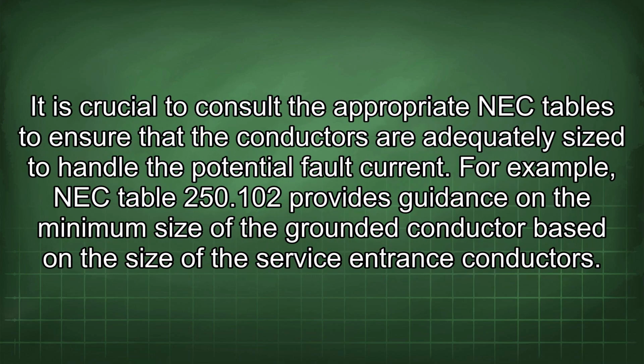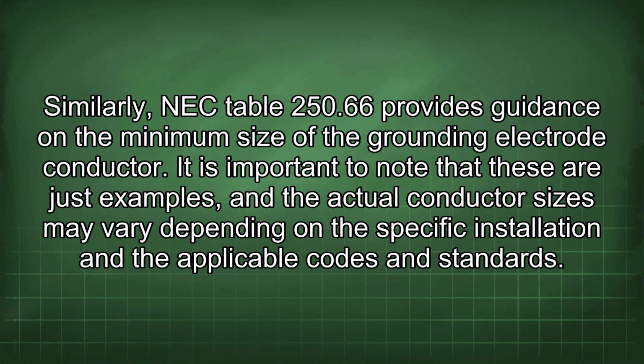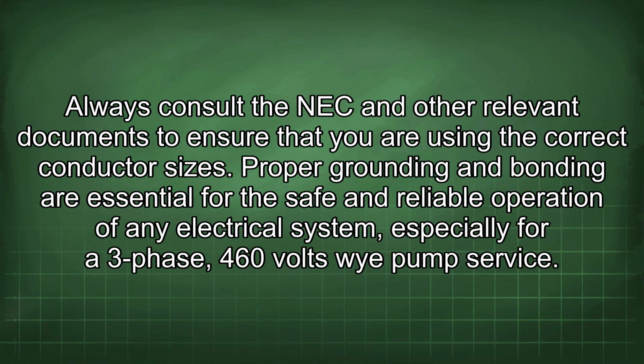It is crucial to consult the appropriate NEC tables to ensure that the conductors are adequately sized to handle the potential fault current. For example, NEC Table 250.102 provides guidance on the minimum size of the grounded conductor based on the size of the service entrance conductors. Similarly, NEC Table 250.66 provides guidance on the minimum size of the grounding electrode conductor. It is important to note that these are just examples, and the actual conductor sizes may vary depending on the specific installation and the applicable codes and standards. Always consult the NEC and other relevant documents to ensure that you are using the correct conductor sizes.